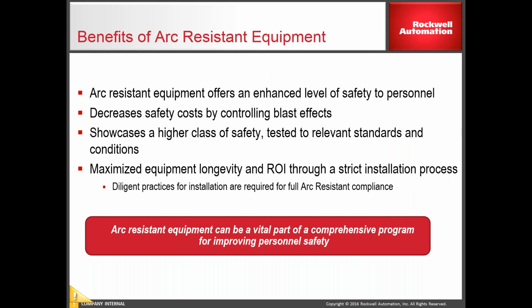So arc-resistant equipment offers a level of safety to personnel. It decreases the safety costs by controlling the blast effects. And you can maximize the equipment longevity and return on investment through a strict installation process. So we have arc-resistant medium voltage MCCs, we have arc-resistant low voltage MCCs, and now we're offering an arc-resistant PowerFlex 7000 medium voltage VFD.